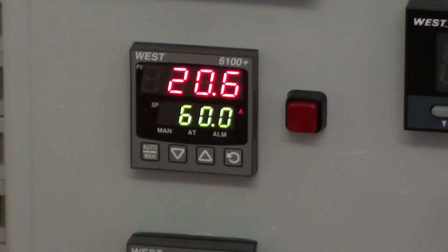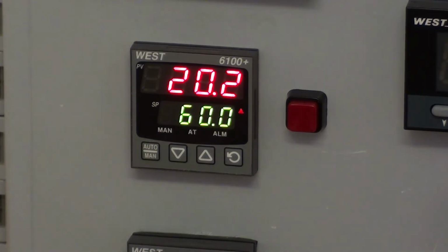The set point ramping feature is selected in the setup menu of the controller. The ramp rate is in units per hour. As we've got a temperature control system, our units are in degrees centigrade, and I've chosen to have a ramp rate of 120 units or degrees centigrade per hour, so 2 degrees per minute.